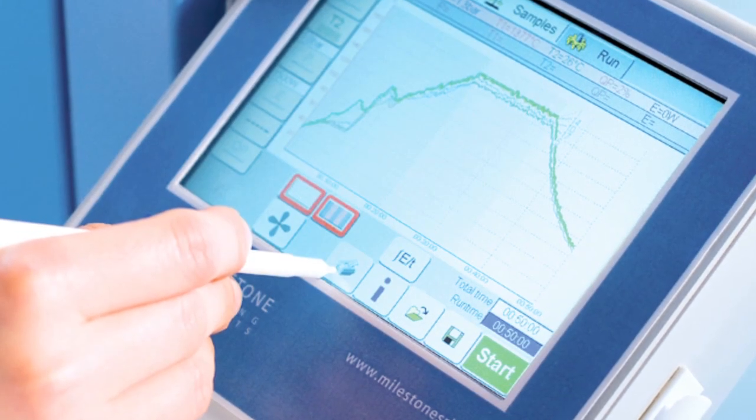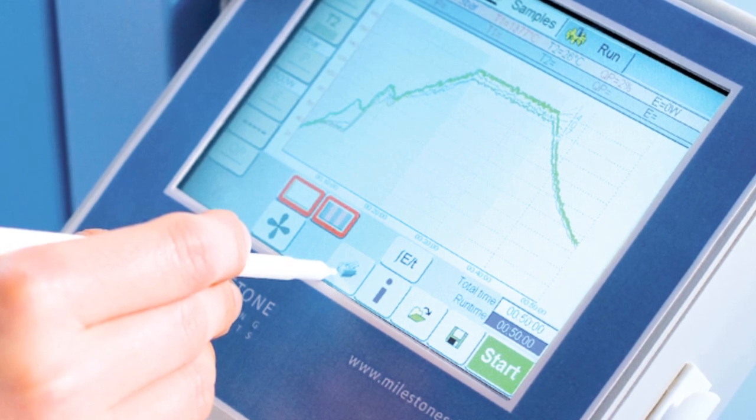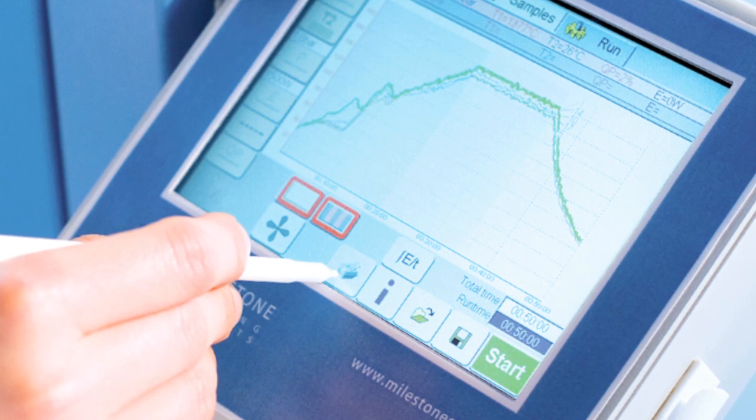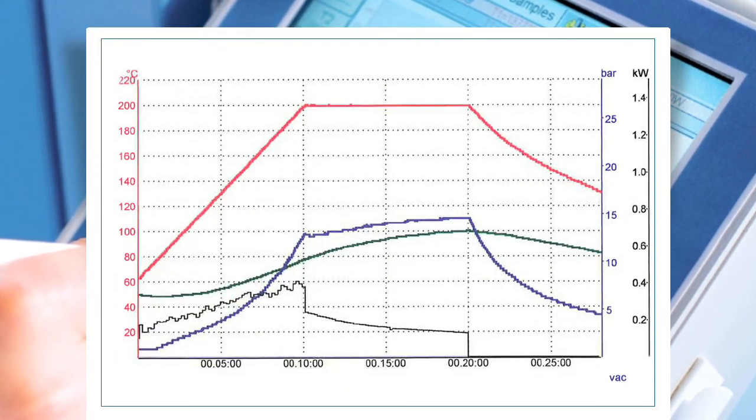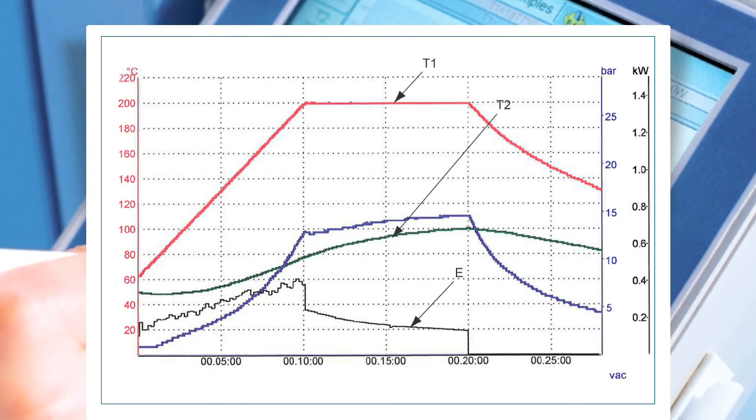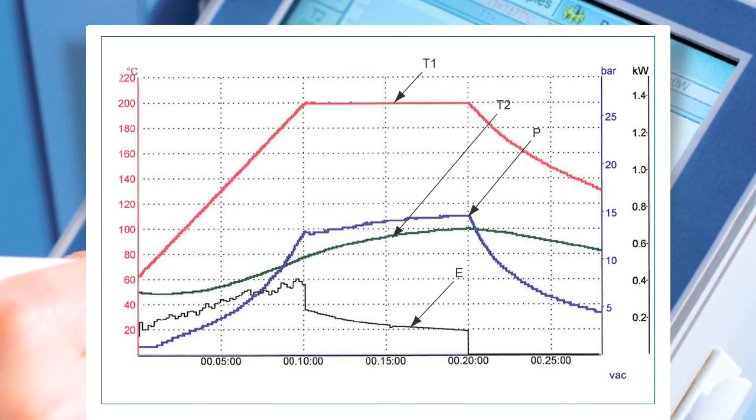Another great feature of EasyControl is that there is no need to select different power levels as the EasyControl's PID controller monitors and records temperature 20 times per second. The system will automatically adjust microwave power output to follow the desired temperature program regardless of rotor or number of vessels being used.